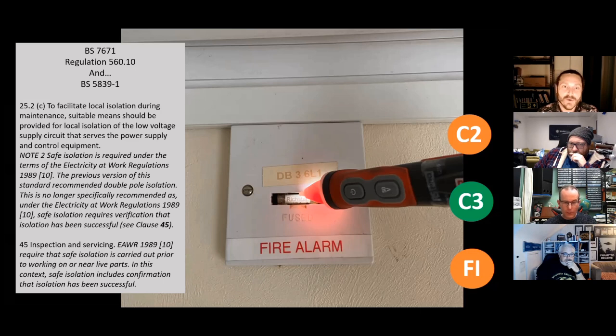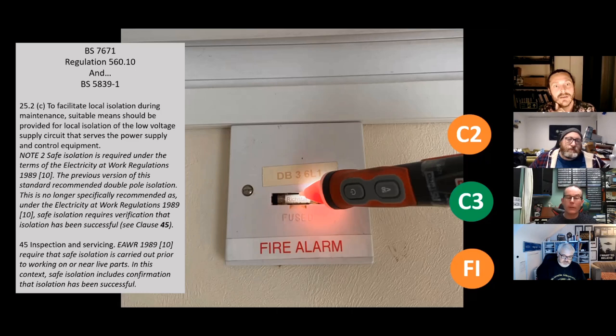So if you had, say, an MK fuse holder, you can actually get padlocks that can go through the fuse holder. So you're not just relying on taking the fuse out, because obviously someone can just re-energise that by putting it back on. But if you use an isolator where it cannot be re-energised without use of a lock-off, that's what should be used as a fire alarm isolator. So that pretty much narrows it down to MK, doesn't it? Because that's with a little hole in the middle. Yeah.